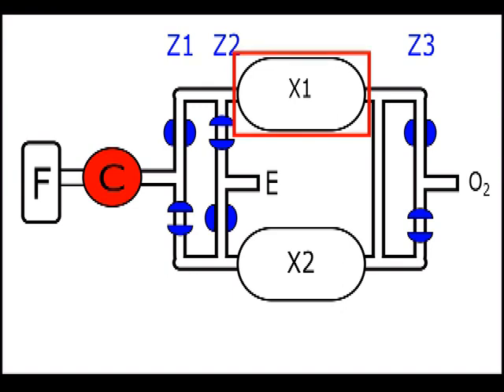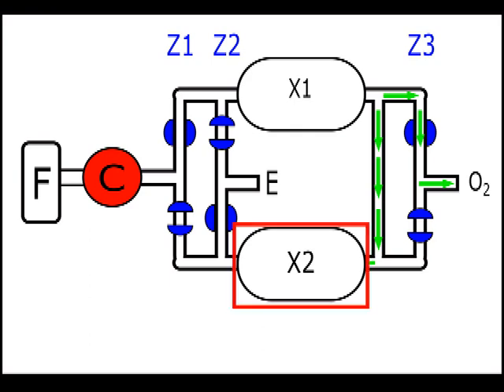This way, 90 or 95 percent pure oxygen flows out from the outlet port of cartridge X1. At the same time, the pure oxygen outlet port also feeds some oxygen to another cartridge labeled X2.